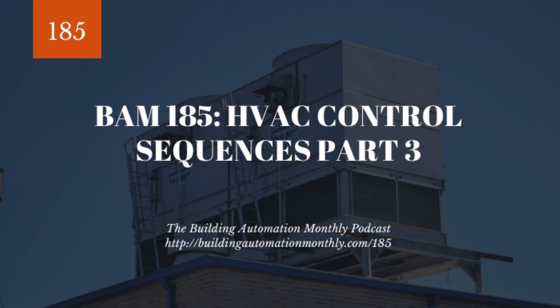All right, so what we also have is CO2 control. ASHRAE 62.1 defines, based on space type and occupancy count, that you must have a certain amount of fresh air within a space, and that's required. Now, what we learn with economizer control is that we can utilize a CO2 sensor, measure return air or space CO2, and then control our economizer position in order to control the CO2 level of the space or the return airstream.